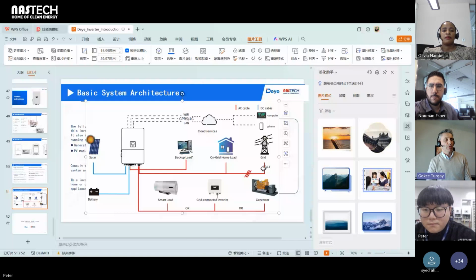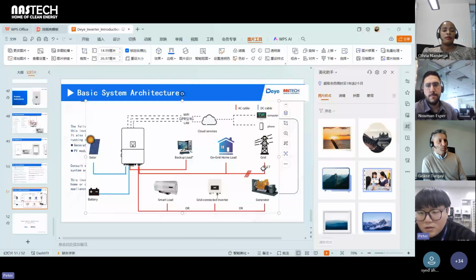Another question. Good question. How do you combine a 60 kilowatt low voltage PV inverter, is it a string inverter? Not clear. And a 15 kilowatt battery inverter in a mini grid setup? If you mean a string inverter, then it cannot use a battery together. But if you mean a hybrid inverter, then it can be done with the battery.